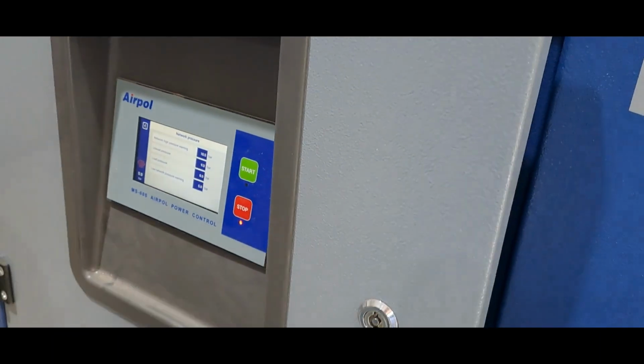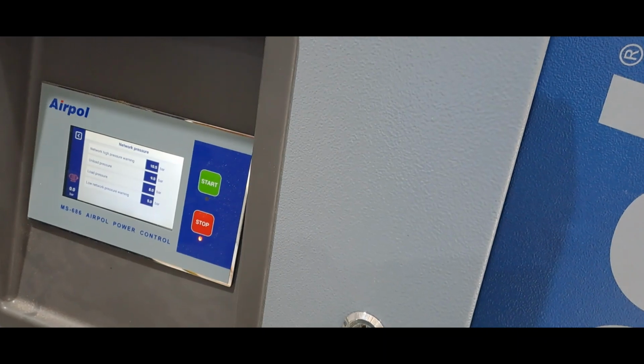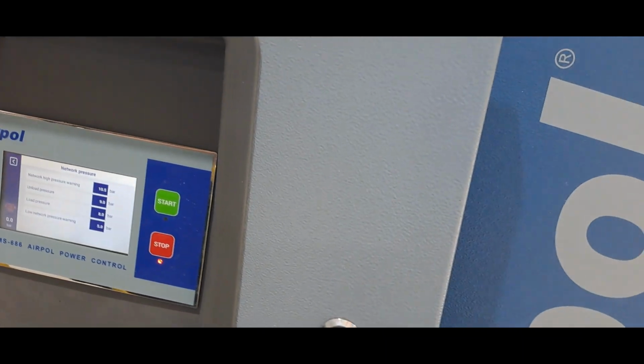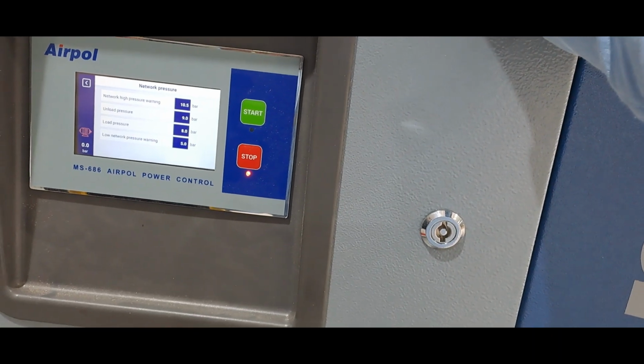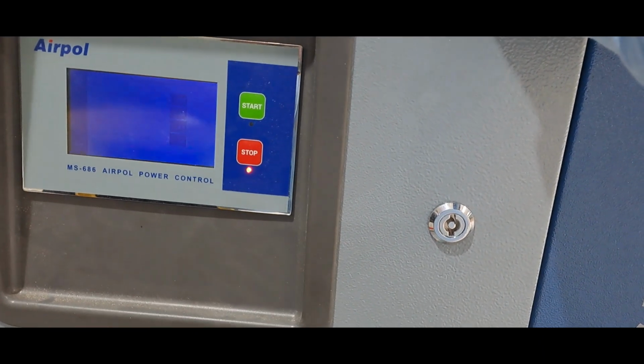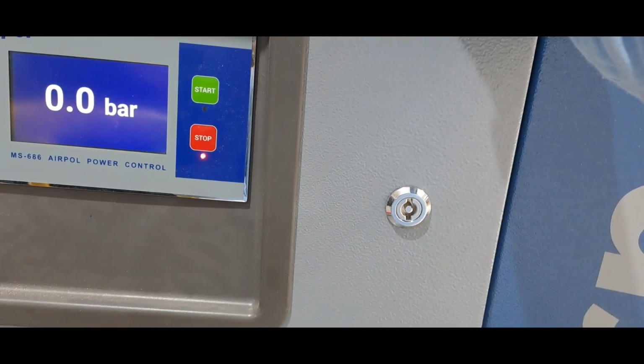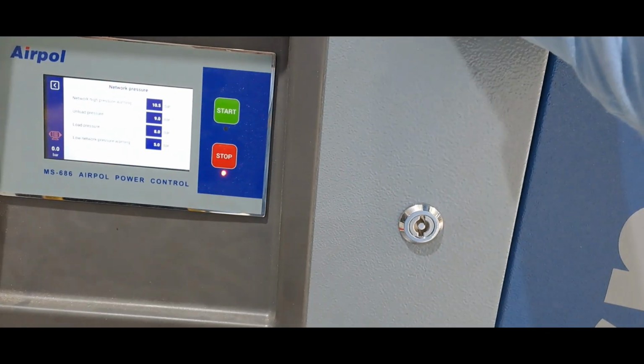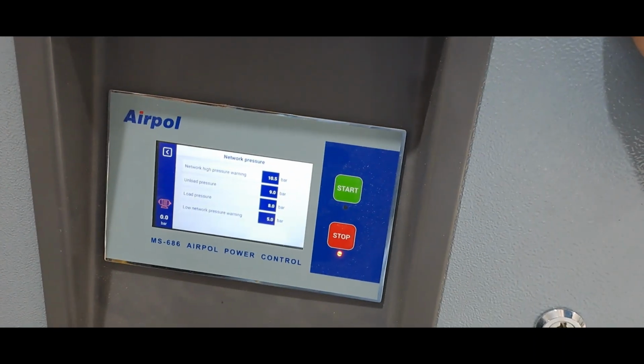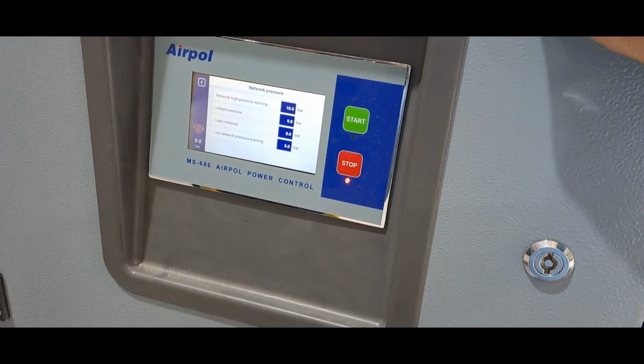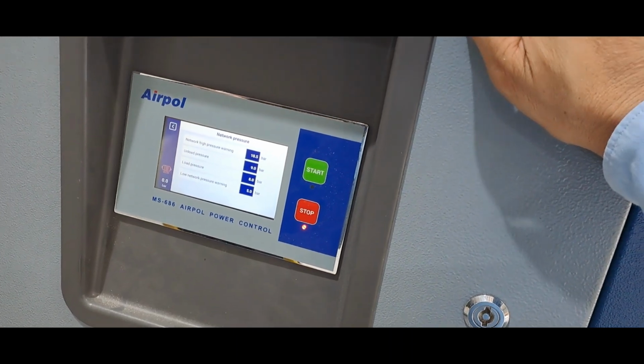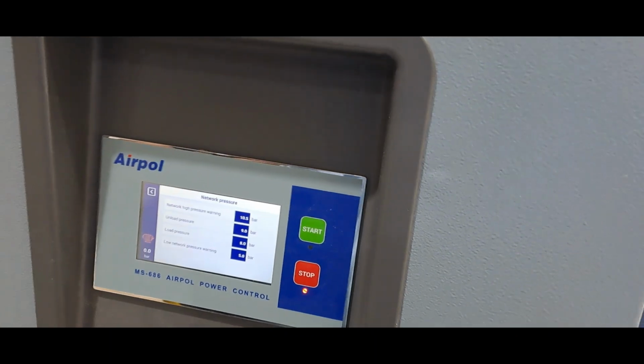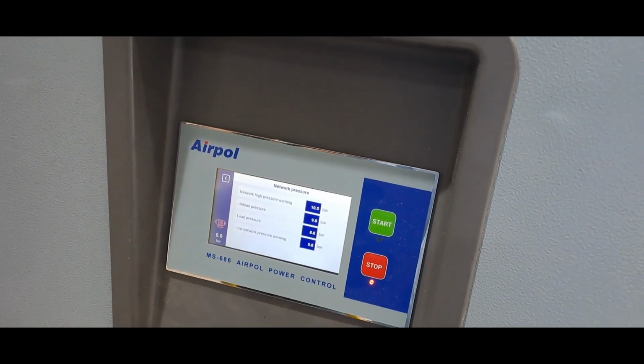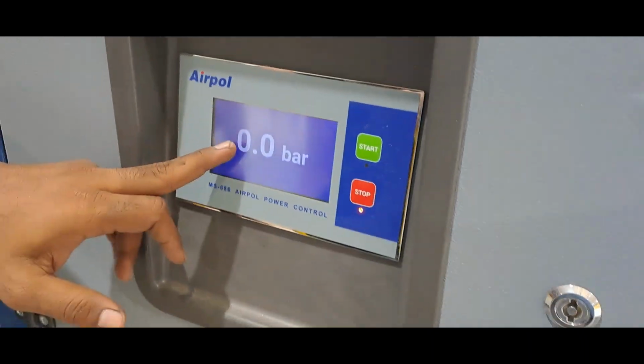Okay, to explain further, cut in means the compressor will start, and cut off means the compressor will stop. So during initial operation, when you press start, it will build the pressure in the tank. When the pressure reaches the cut off pressure, which is 9 bar, the system will unload, and after some time, if there is no consumption, the compressor will turn off by itself. When consumption happens and the pressure goes down to 8 bar, the compressor will automatically restart by itself until it reaches the nominal pressure and the cut-off pressure. So if there is consumption, the compressor will continuously produce compressed air until it reaches the maximum cut-off pressure of 9 bar. Okay, so the pressure differential is 1 bar.